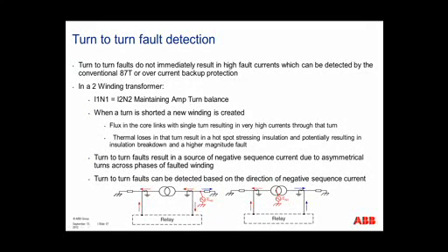Okay, next question is, what is a typical setting for negative sequence turn-to-turn fault protection? I've seen it set to 10% per unit. That's the typical setting our relays use. So if you see anything greater than 10% per unit of your rated current, and that's based on that differential, so any excess differential current over 10% per unit.